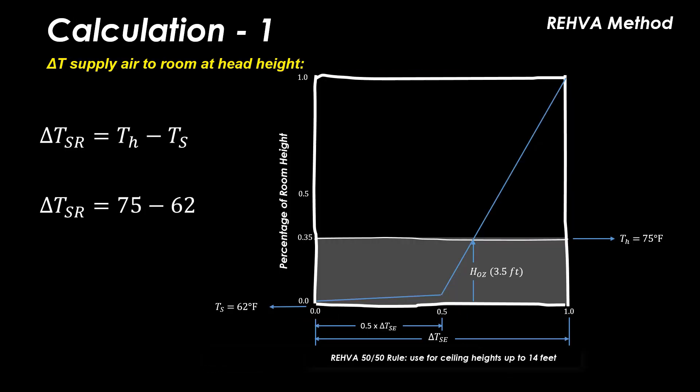So now that we have established some starting parameters, I will go through the calculation process step by step. The first is a calculation to determine the temperature differential between the supply air from the diffuser to the room temperature at head height or space control temperature. Simply subtract 62 from the 75 head height temperature resulting in a delta T of 13°F.